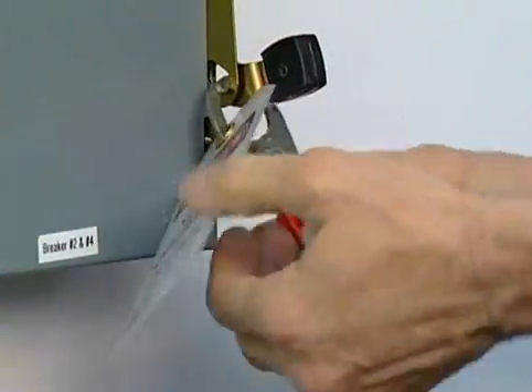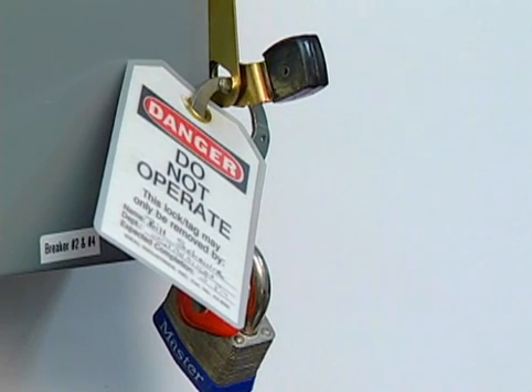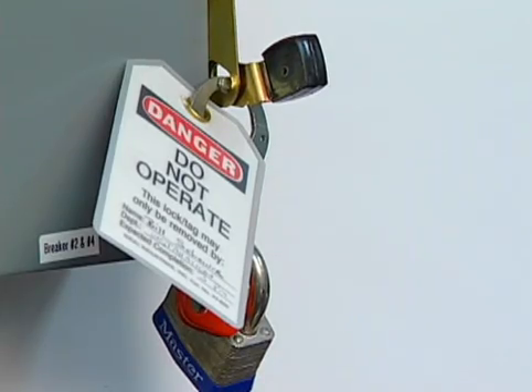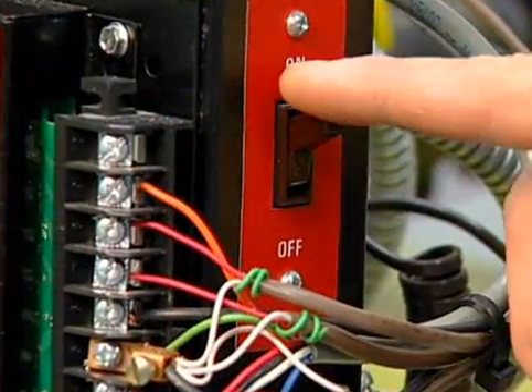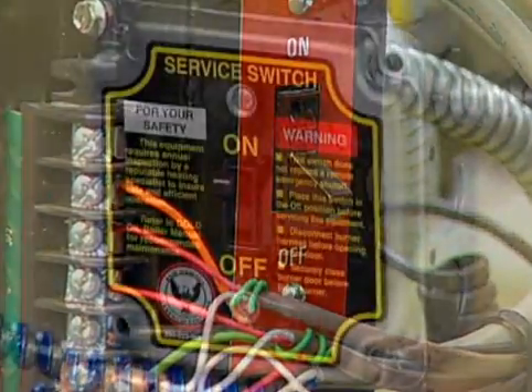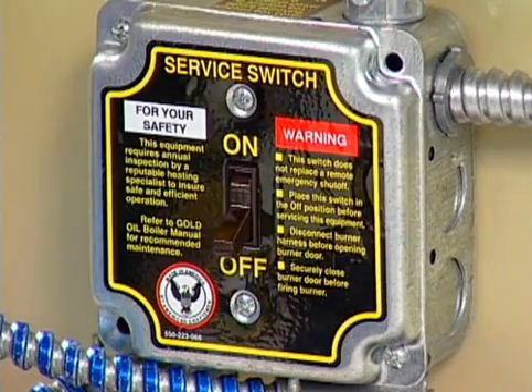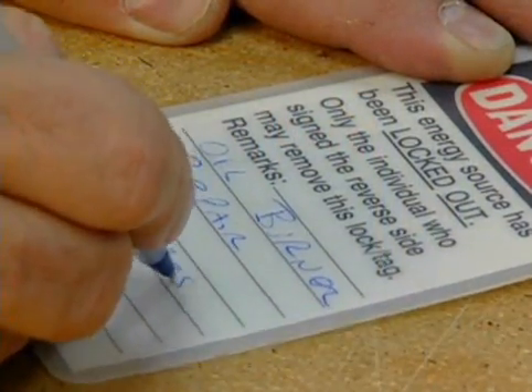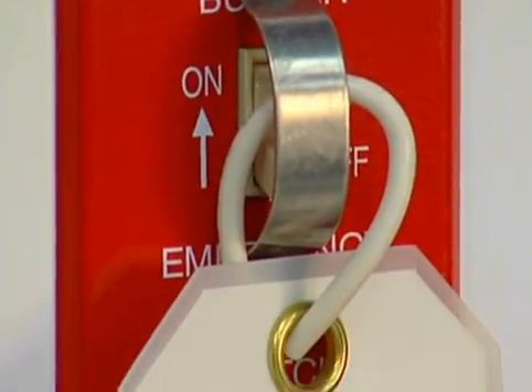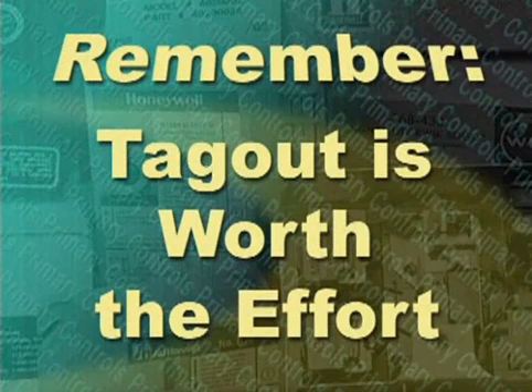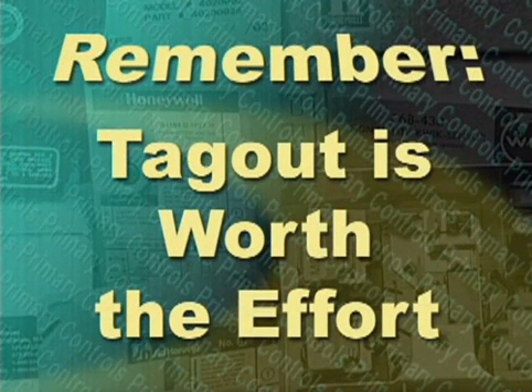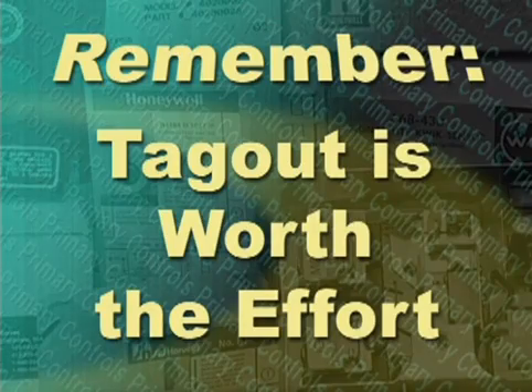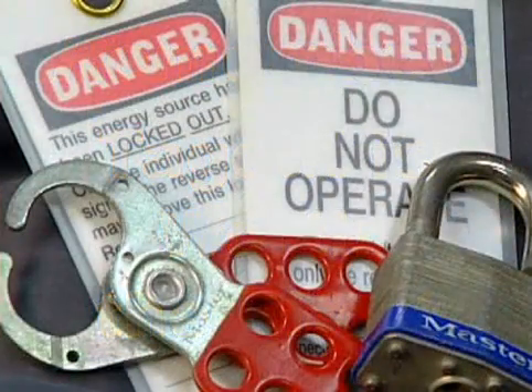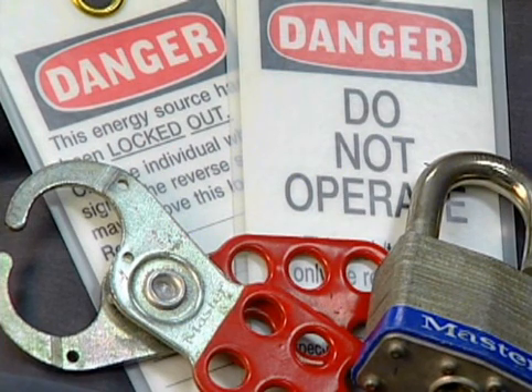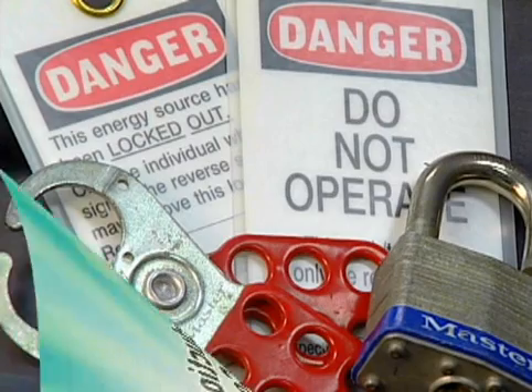Lockout involves applying a physical lock to the power source of circuits and equipment after they've been shut off and de-energized. Then tag out the circuit with an easy-to-see sign or label that lets everyone know that you're working on the circuit. Since equipment lockout often isn't practical, OSHA considers shutting off the equipment in 2 places as the equivalent of lockout. For example, tag out without a lockout will be adequate if the equipment is shut off and tagged at both the breaker and at the unit. Remember, while tag out might take a few extra moments, it's worth the effort to prevent someone from accidentally energizing a circuit while you're working on it. In this video, when we say turn off the electrical supply, we're referring to lockout tagout.